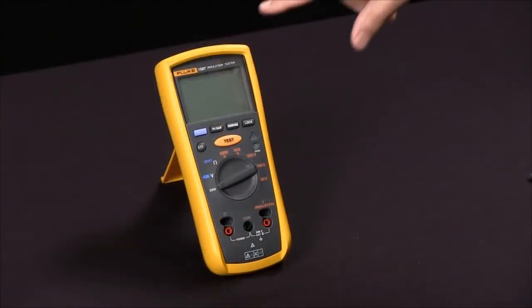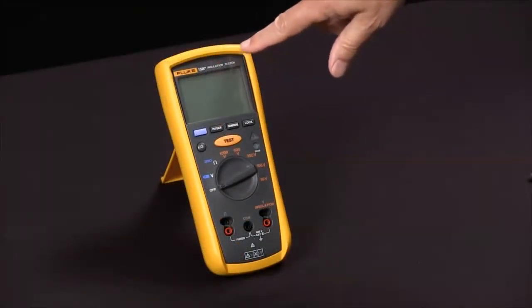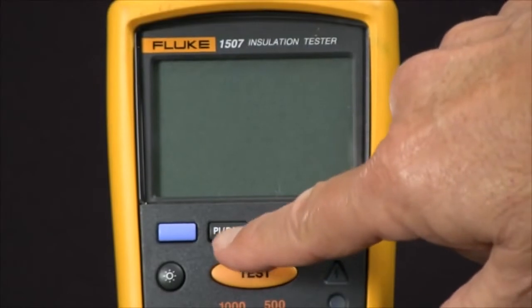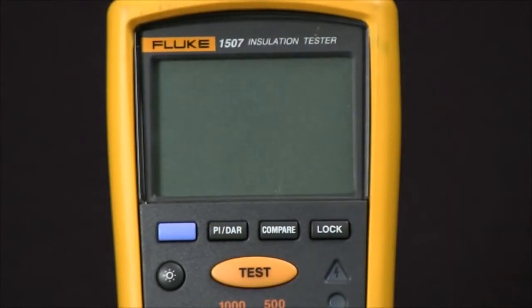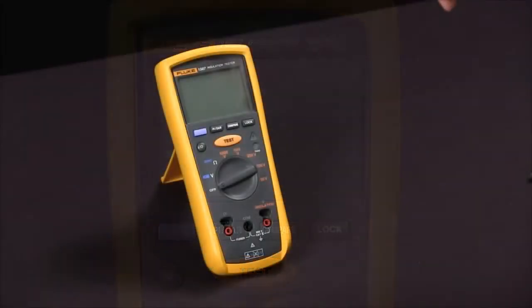To use our Fluke 1507 insulation tester, we have two automated functions. Polarization index, which is a 10 minute to 1 minute ratio time test, and dielectric absorption ratio, which is a 1 minute to 30 second test.